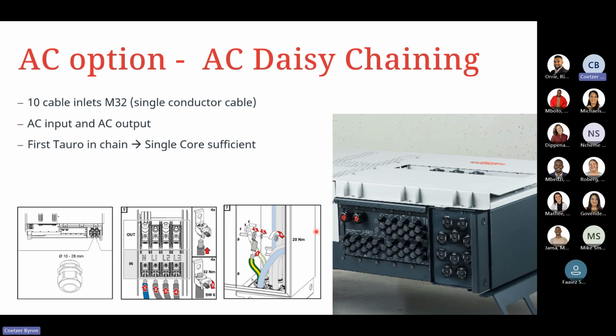This allows us to get away with a reduction in cable costs on the AC side because we can simply run one cable for every 4 units on the 50 kilowatt variant. We've got a 200 kilowatt limitation for the last inverter to push that cable back to our distribution board. So we can either have 4 by 50 kilowatt units in the series or 2 by 100 Fronius Tauros. That way we get away with using less AC cable, again bringing down our BOS in terms of the system itself.